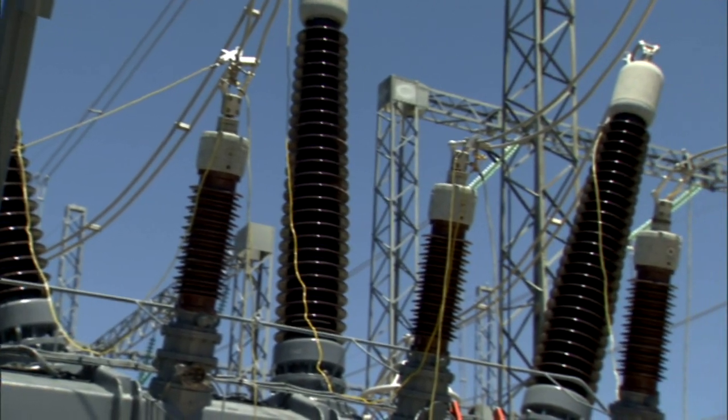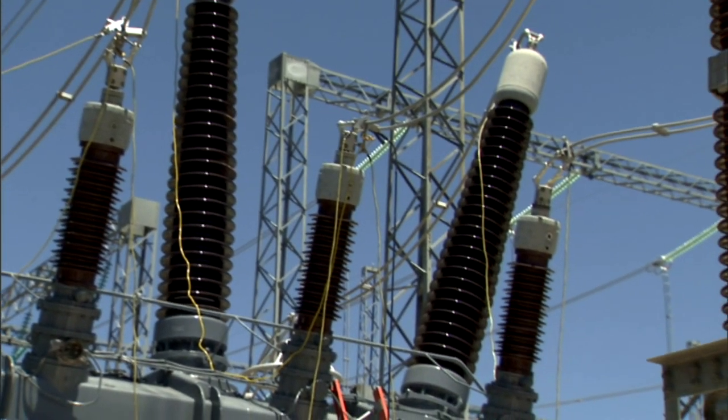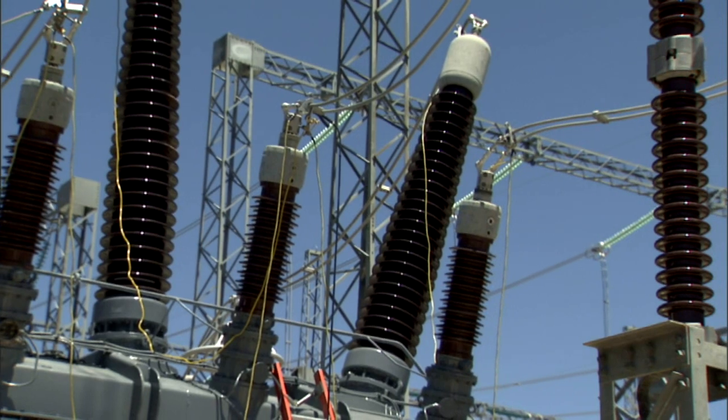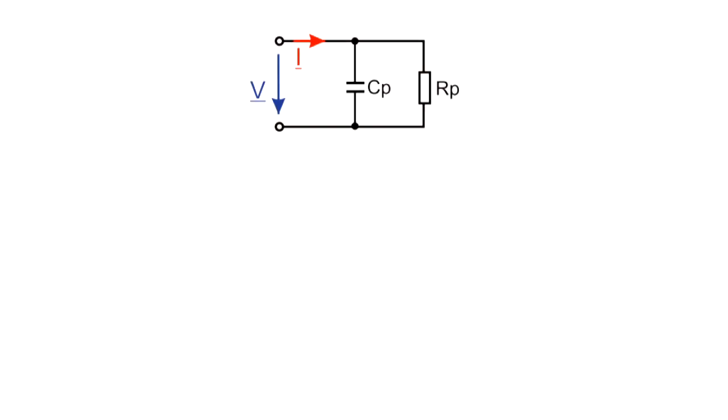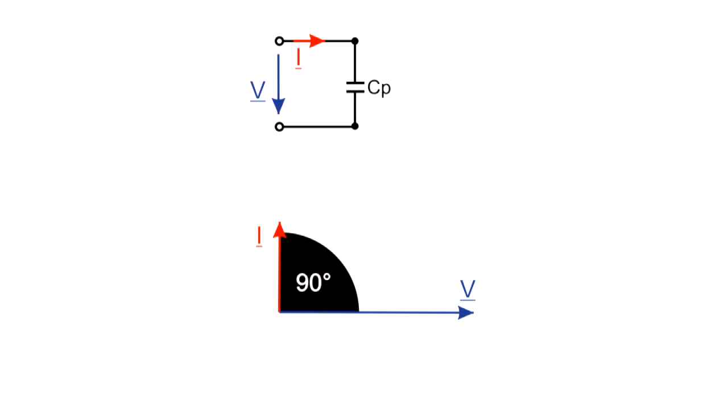At a particular frequency, for example 50 or 60 Hz, the behavior of the insulation can be represented with an equivalent circuit consisting of an ideal capacitor with a resistor in parallel. An ideal capacitor has no losses and a phase angle between the voltage and current of 90 degrees.